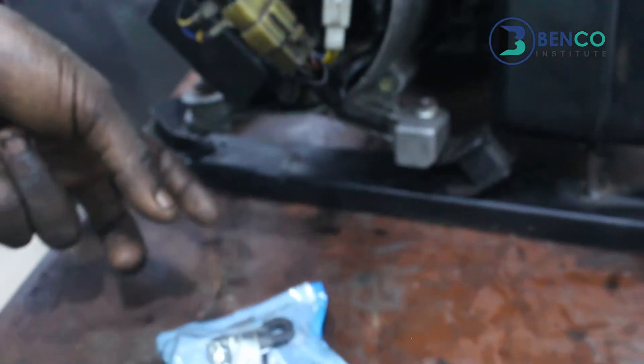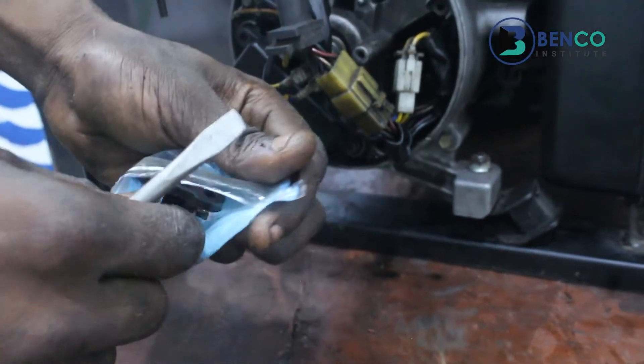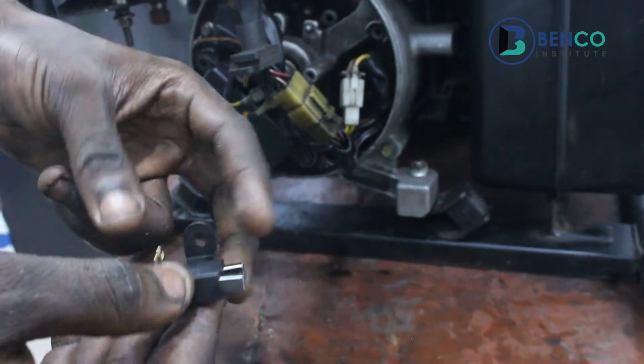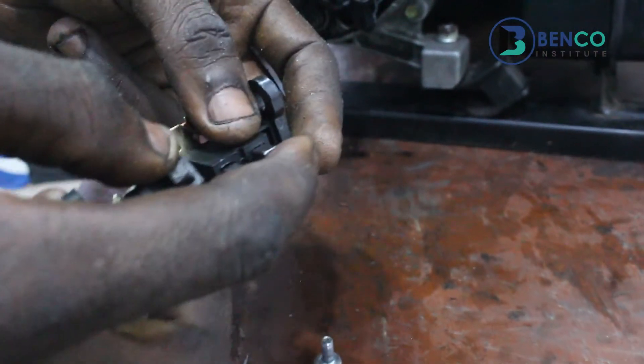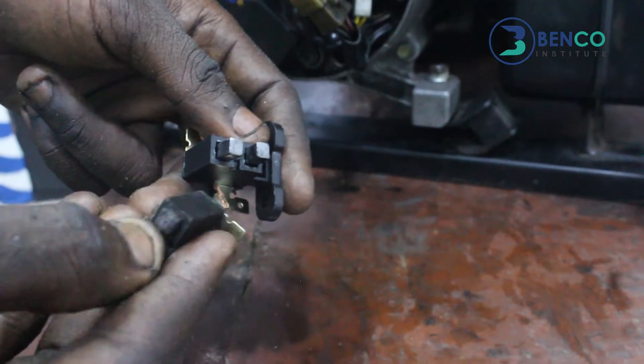So what we'll be doing now is we'll be changing it — using another one. We got another brush from our shop. You can check out the link shop.bencoengineering.com in the description below. You can see the big difference — it's quite a huge difference. You can see these carbon rods; they are made of carbon. The carbon rods are very much erect, but this one, after working and working, has been eaten down. So we just need to fix it.